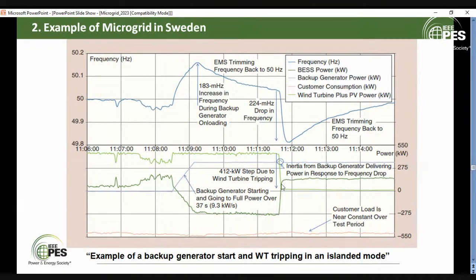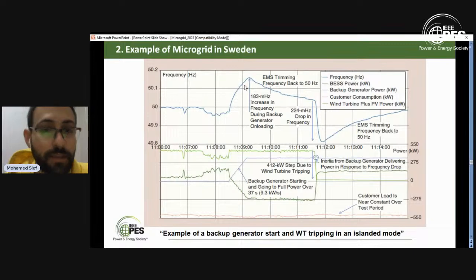At this time, it really compensates for this. The wind turbine is tripped and the battery energy storage system is restored, allowing the frequency to reduce along the frequency curve because we lost a rotating machine. In the first case, we added a rotating machine, the diesel generator, so the frequency increased steeply. Here we lost a rotating machine, the wind turbine, so the frequency reduced very much, and the energy management system restored the frequency back to 50 hertz.